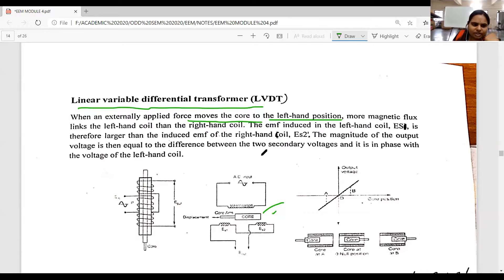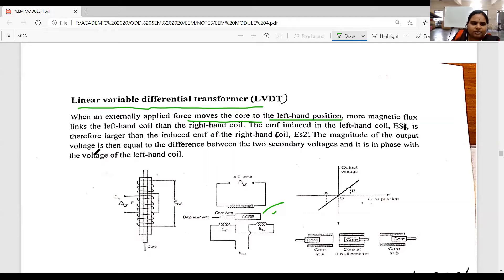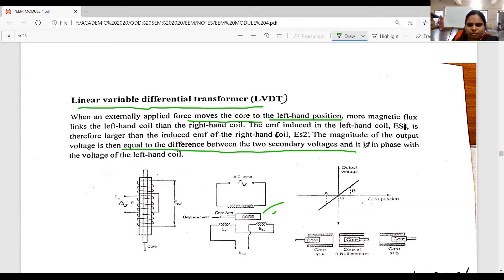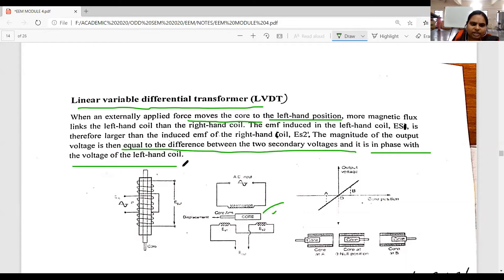The EMF induced in the left hand coil, that is ES1, is therefore larger than the induced EMF in the right hand coil, that is ES2. The magnitude of the output voltage is then equal to the difference between the two secondary voltages, and it is in phase with the voltage of the left hand coil.